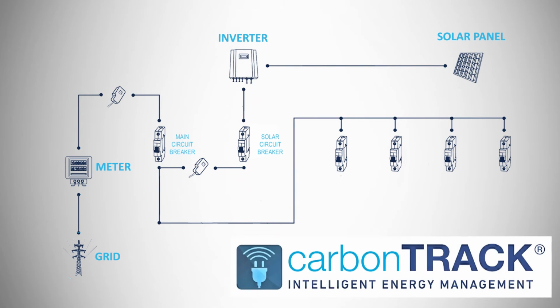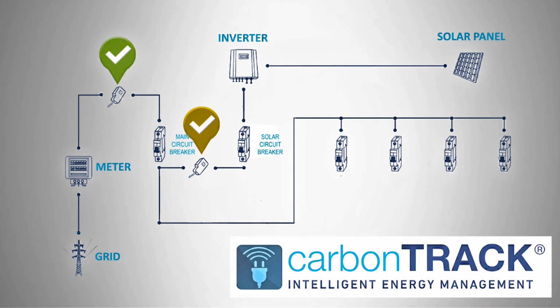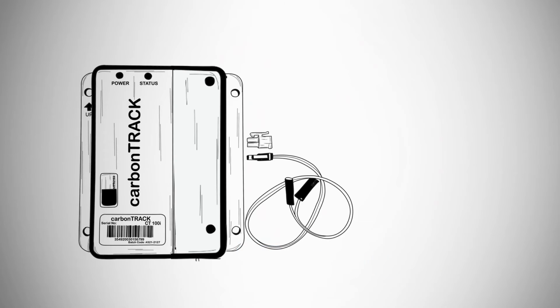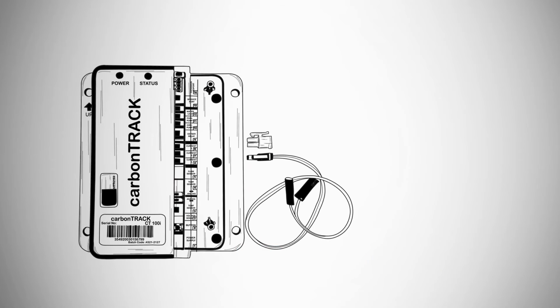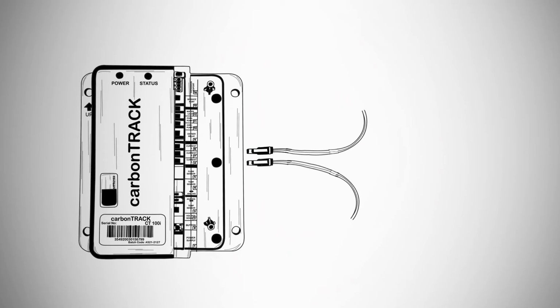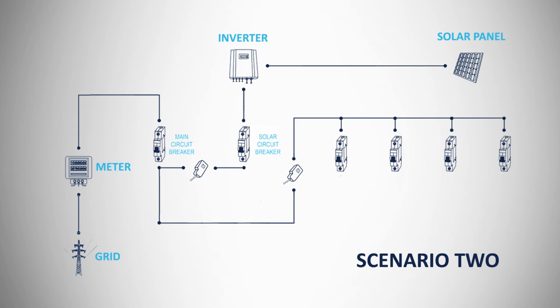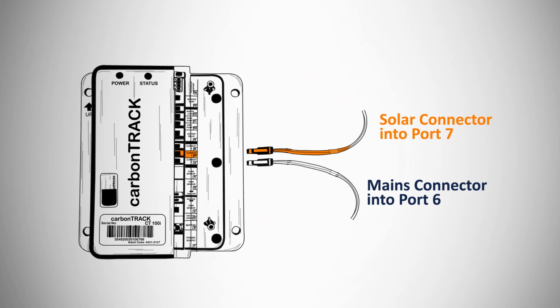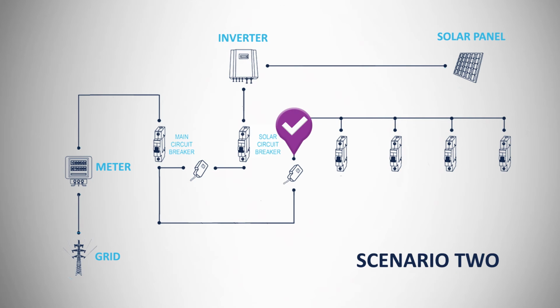Install 1 current clamp on the mains wire between the meter and the mains breaker. Install another CT on the live output wire of the inverter. Next, remove the CT100i service cover. Run both current clamp cables into the CT100i enclosure. Plug the mains clamp connector into port number 6 of the CT100i. Plug the solar clamp connector into port number 7.